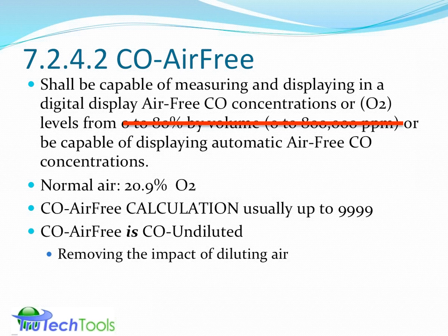So we're talking about basically CO air-free concentrations, and it's probably going to say up to 9,999 or some level like that is the concentration range for the CO air-free calculation. Some products call CO air-free "CO undiluted" or "undilute." That means it's doing a calculation to remove the impact of the diluting air, the air that gets into the flue gas stream either through the combustion chamber, or through draft assist, or through ventilation air or combustion air, that would throw off the CO calculation, just the raw CO number, by diluting it. We're going to get into this concept in the next slides to crack that open and explain the science behind the CO air-free calculation, what it means and how it's going to work.